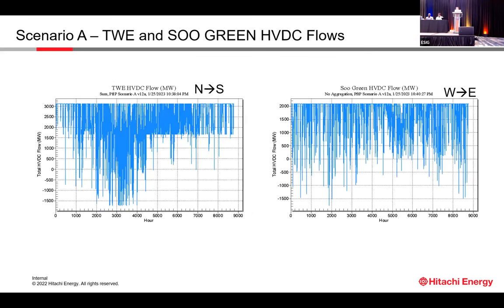This is looking at the production cost simulation, and the Transwest Express is utilized significantly. You can see there's a clip in both directions, positive and negative, at about 1600 megawatt. This is because of the AC transmission connection limitation at the two transformers, which is 1600 megawatt. So this is the Transwest Express. The SOO Green Line is west to east, so its utilization looks like this.